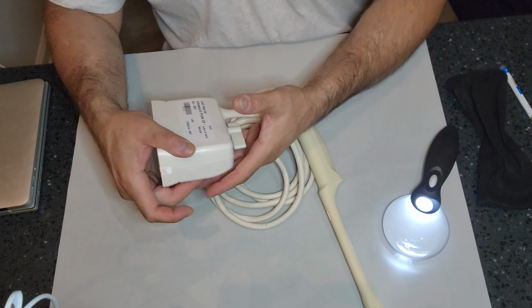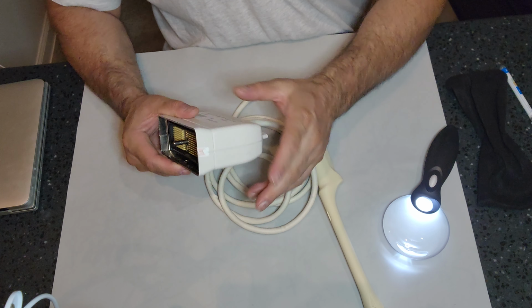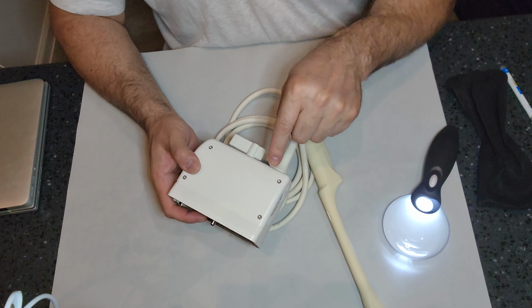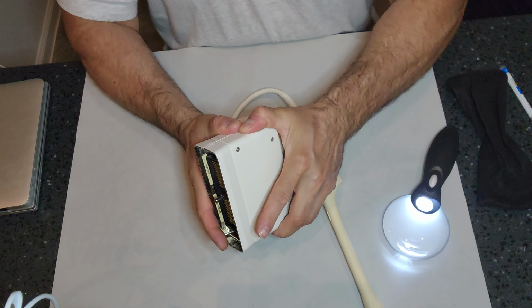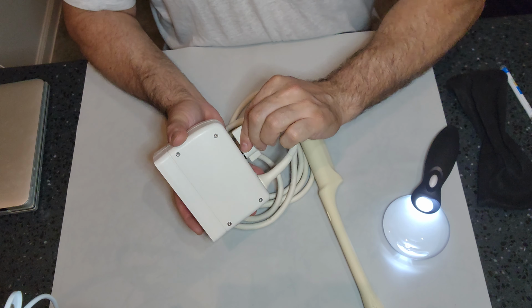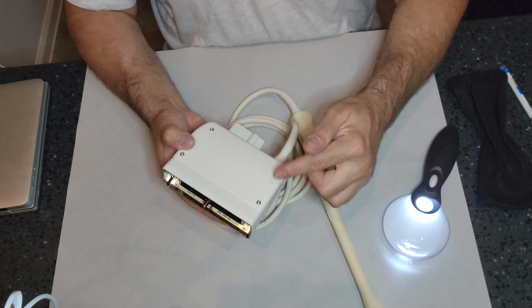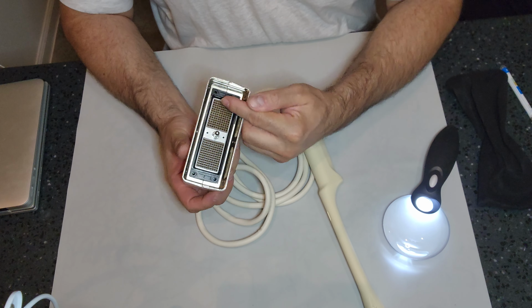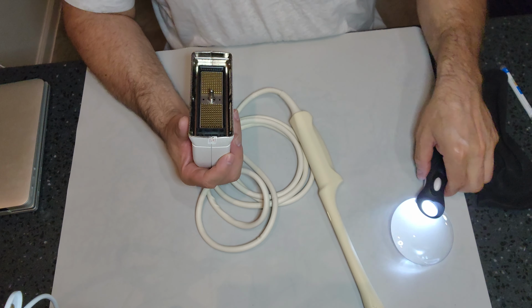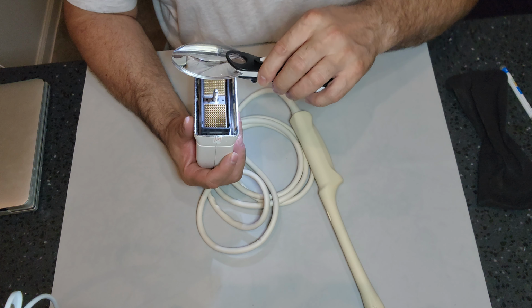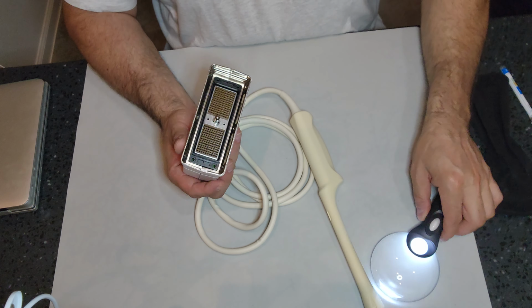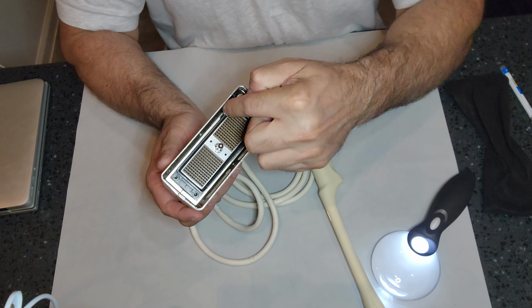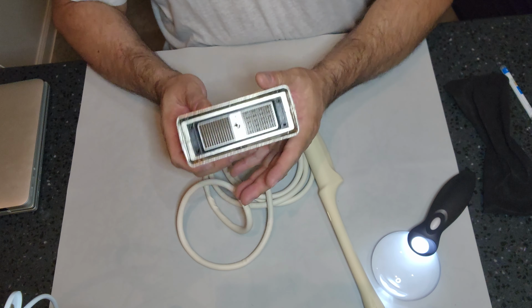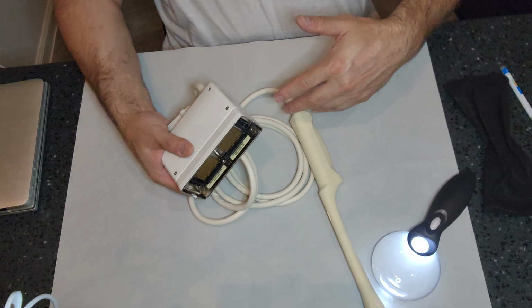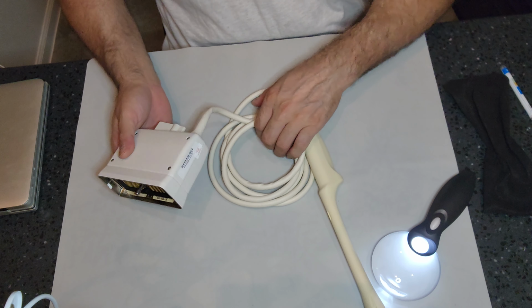When you get to your connector box, is it cracked? Is there a screw missing? Is it loose? Can you open it? Can you move it? Does the lock work? Check all that. Look at the probe. Look at the connectors. Is there any corrosion on the connectors? Is there a crack in the seal around the box? All those need to be inspected before we go into our next step.